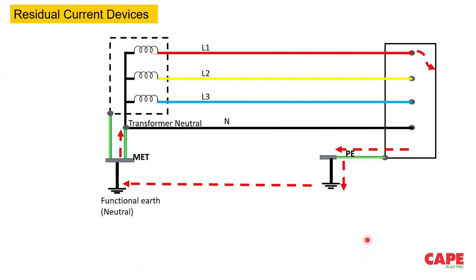Nowadays, we use a device called a residual current device, RCD. RCD works on another principle. Here, the sum of the currents is measured, and residual current, for a layman, you can think of it as a current which is escaping from the circuit. So in case of any leakage through a different route, that particular current is measured with this mechanism, and it disconnects the circuit automatically. As a result, safety is achieved.